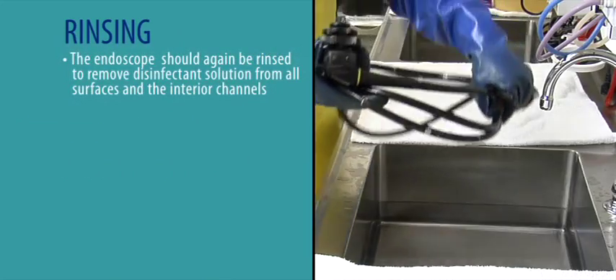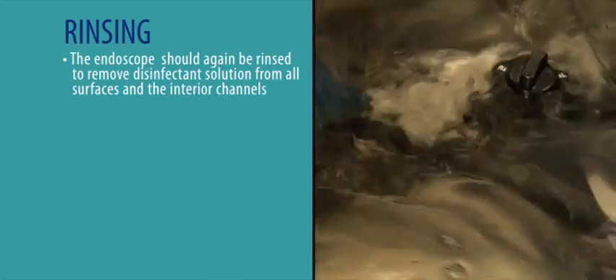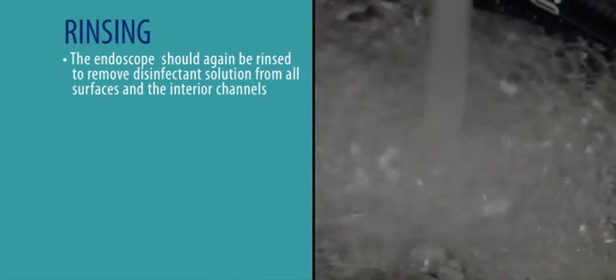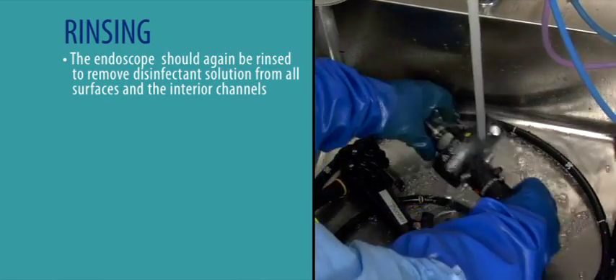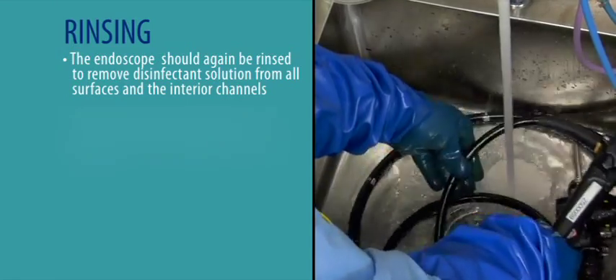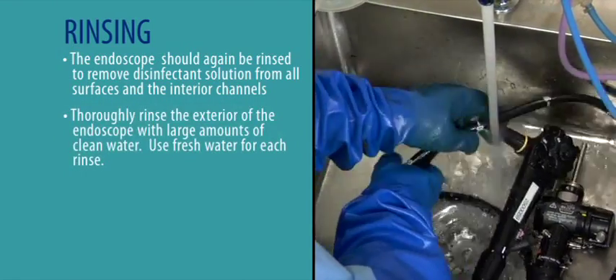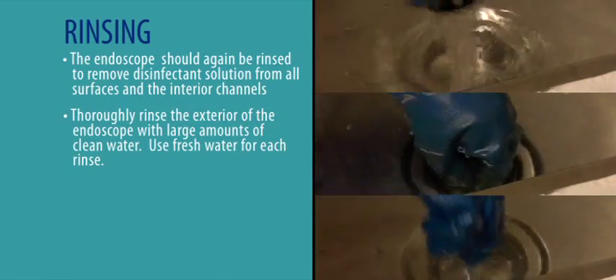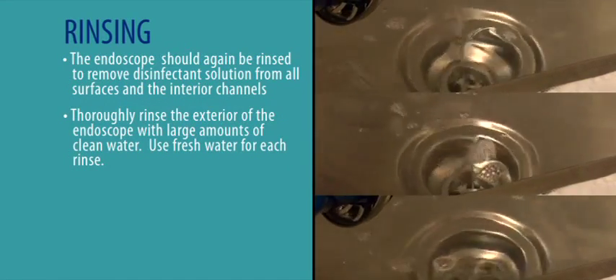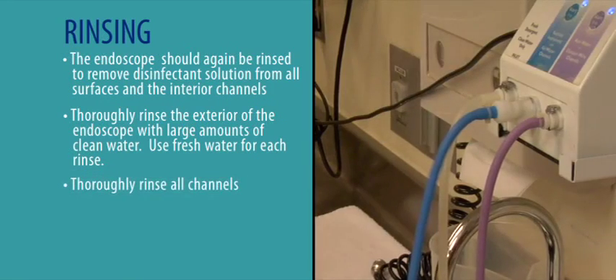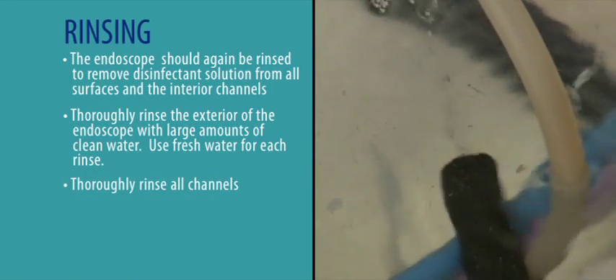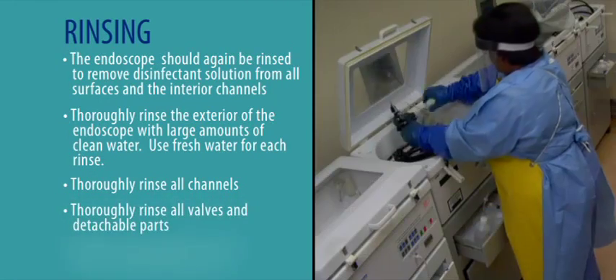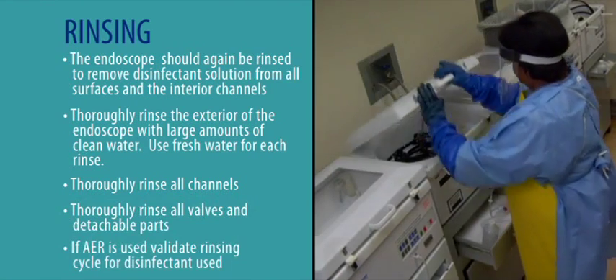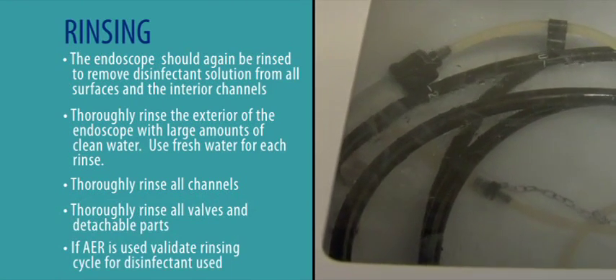6. Rinsing. The endoscope should again be thoroughly rinsed to remove disinfectant solution from all surfaces and the interior channels. Residual disinfectant can be harmful to the patient's delicate mucosa. Thoroughly rinse the exterior of the endoscope with large amounts of clean water. Use fresh water for each rinse. OPA requires 3 rinses. Thoroughly rinse all channels with large amounts of clean water by flushing with the channel adapter. Thoroughly rinse all valves and detachable parts of the endoscope. If an AER is used, ensure that rinsing cycles have been validated for the high-level disinfectant used.